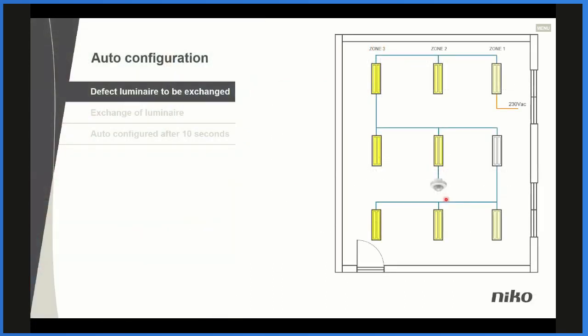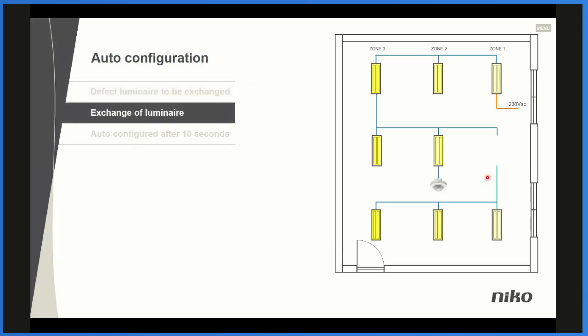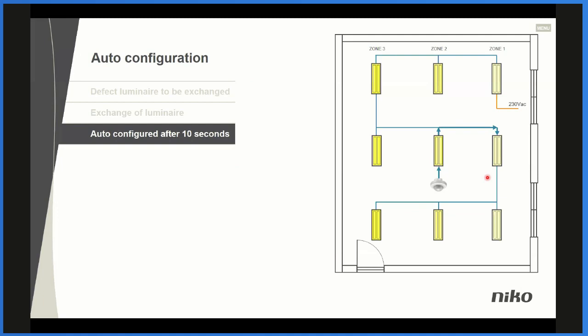If you had a little illustration of how it's operating, this luminaire at the right-hand side is broken and it had to be replaced. We just replaced the luminaire, put in a new one, and when it is done, we power up again, and within 10 seconds, all the settings from the previous, broken luminaire have been adapted to the new luminaire. The detector has the same settings put in the database. That means in its database here in the detector, it has all the data for each and every luminaire that we have on the DALI bus here. So that's a quick way to do it.